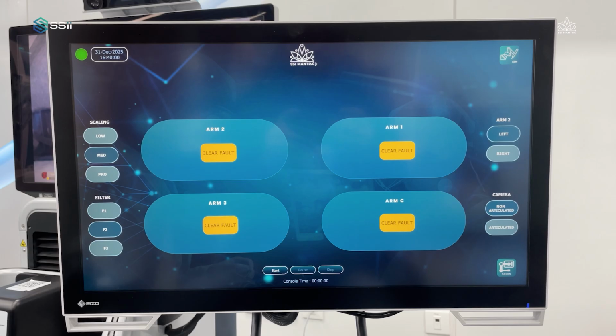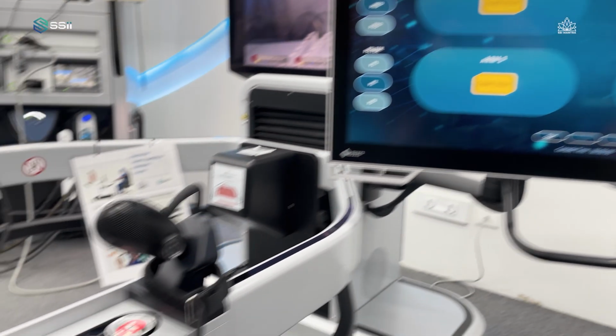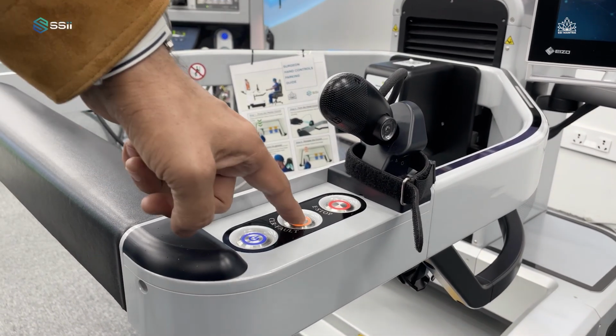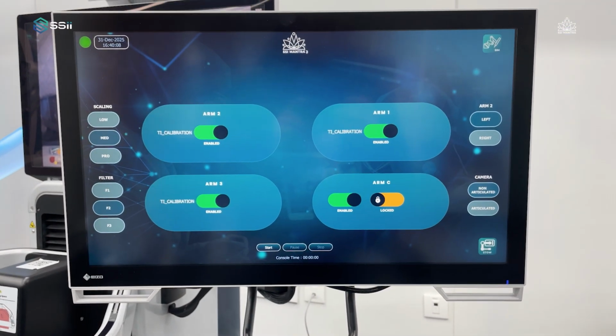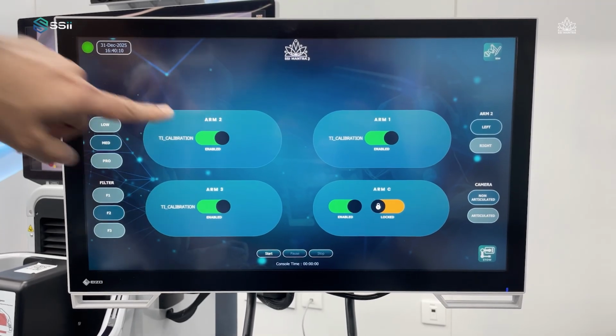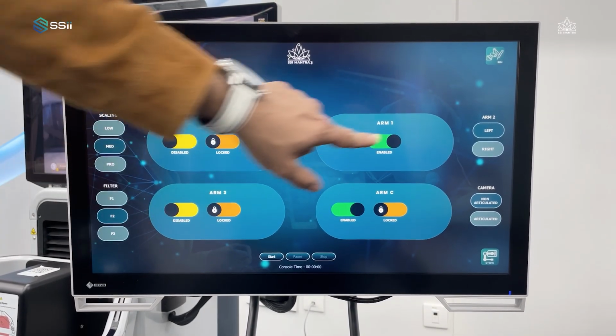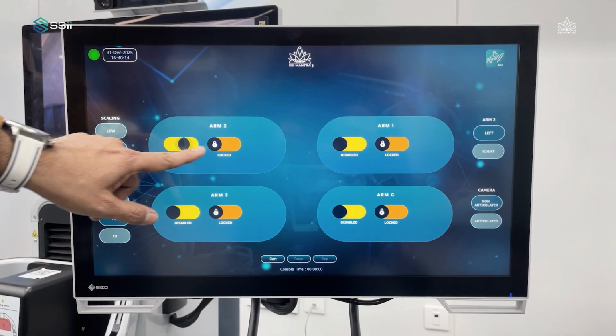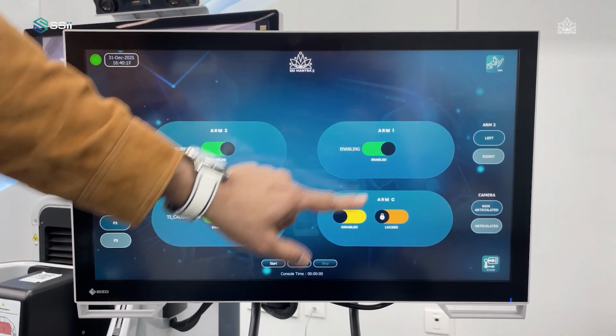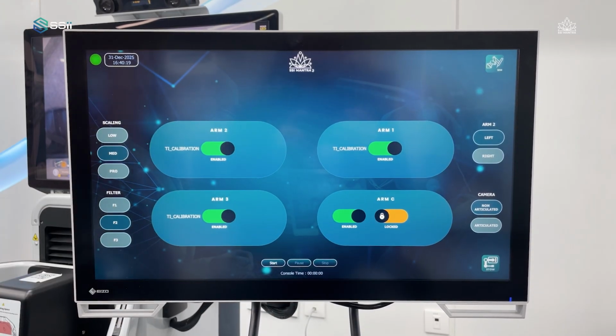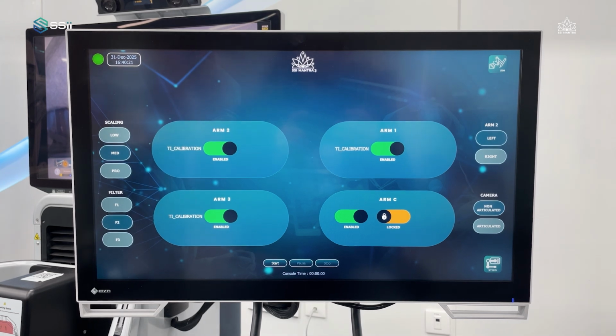To recover, press the clear fault button for each arm on the SCC 2D screen, or press the clear fault button on the SCC control panel to clear faults on all arms simultaneously. After clearing the faults and before enabling the arms, ensure that no instrument or endoscope is mounted on the system. Enable each arm twice as instructed and allow the system to complete TI calibration before mounting any instrument or endoscope.